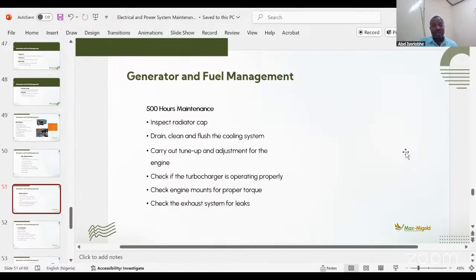At 500 hours, this is what you do: check the radiator cap, there may be deposits of debris that will trip the sensor and cause the generator to keep shutting down. So paying detailed attention is key in maintenance.